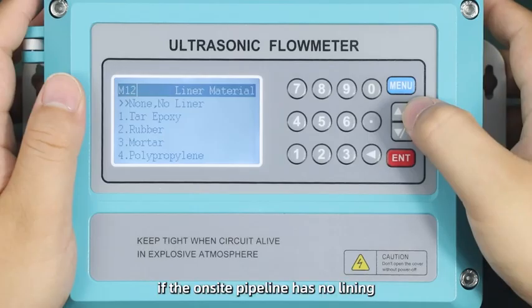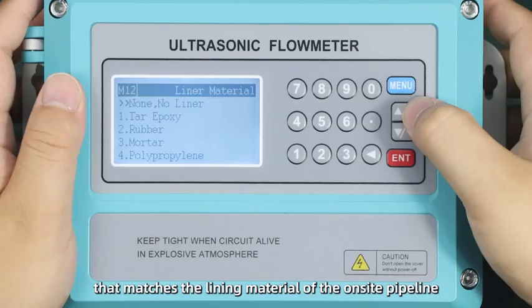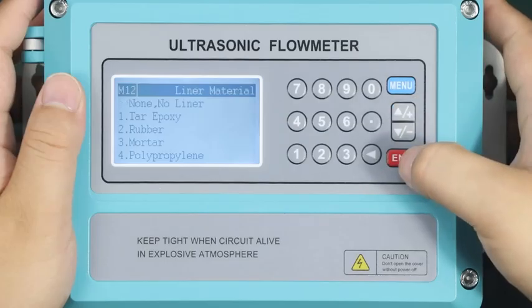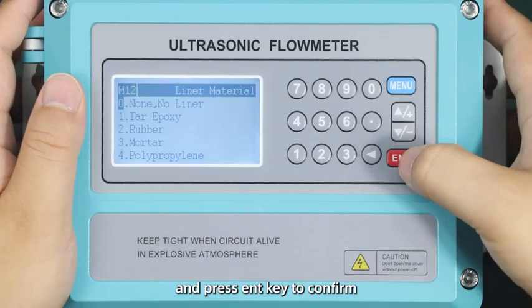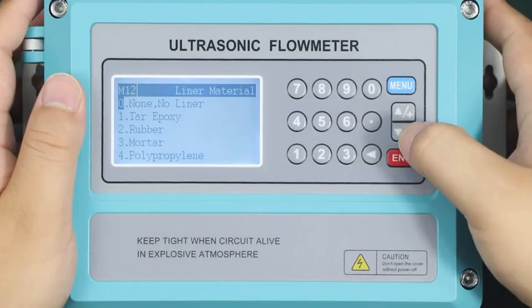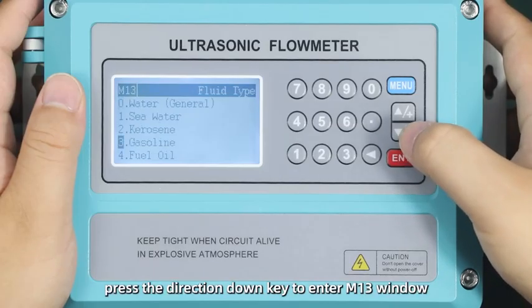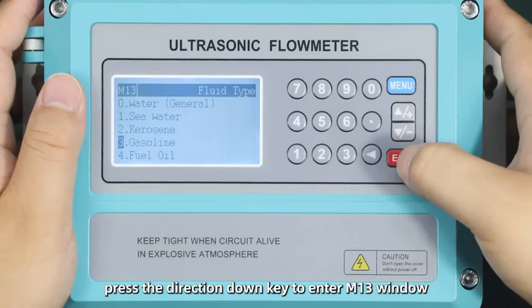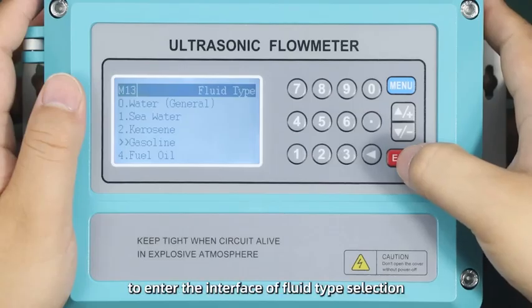If the on-site pipeline has no lining, select the unlined option. If the on-site pipeline has lining, you need to select the option that matches the lining material of the on-site pipeline, and press Enter key to confirm after selection. Press the direction down key to enter M13 window. Press Enter key to enter the interface of fluid type selection.